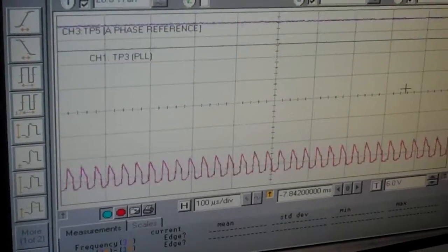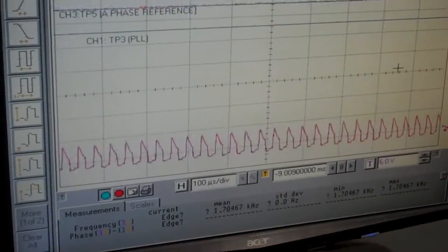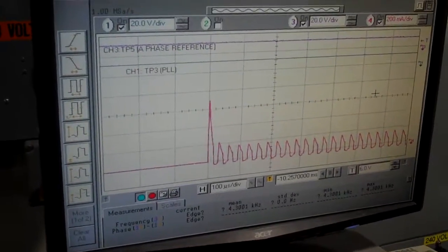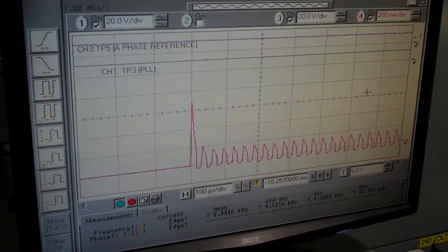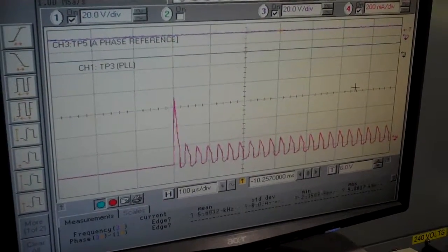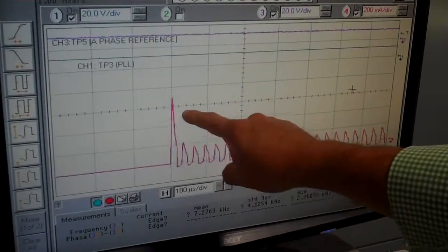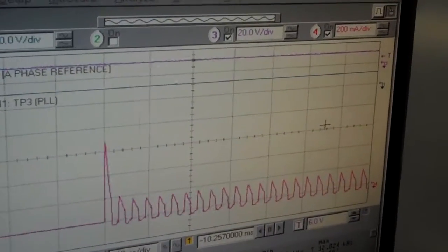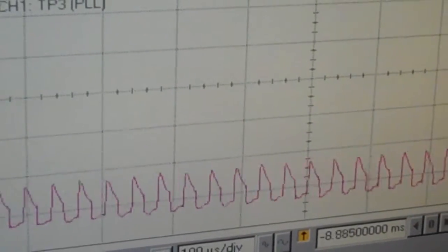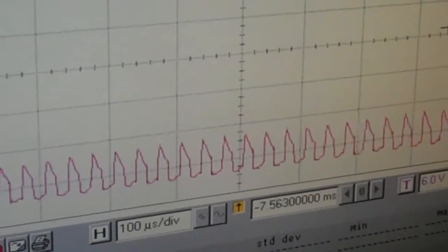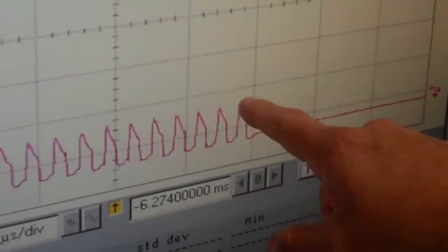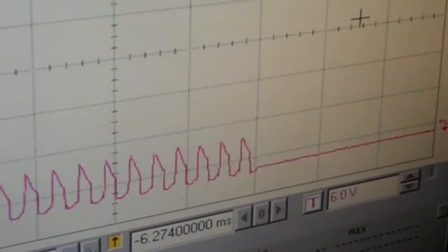And I'm going to open this up. The reason why I'm checking the 120 as opposed to the 230 is because these are the worst loading conditions. The firing board is giving you an output. So if we were to measure that, it is at approximately 3.5 divisions. So that's a peak of 700 milliamps for the initial, and if we go all the way to the end of that, it's at approximately 150 milliamps.